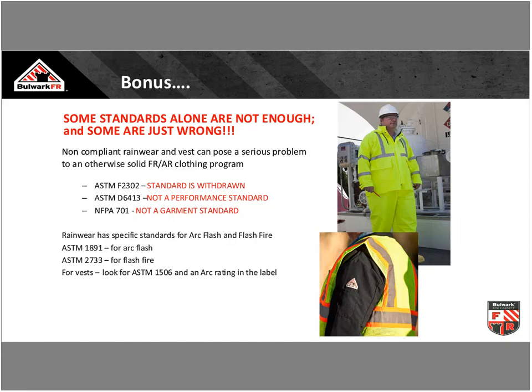The other thing to think about now is we've got a lot of companies that are adopting FR vests, especially ANSI 107 2015 compliant vests. Read the labels. Make sure in that label it tells you that ASTM 1506, that's how it became FR, and you've got an arc rating in that label. If it doesn't have an arc rating, if it tells you some silly things like it self-extinguishes, but there's no arc rating, there's no reference to 1506, wrong vest. We see vests that are compliant to an NFPA 701 standard. That's not even a garment standard. That's a drapery linen standard for the hospitality industry. It's a topical treatment in many cases, and it should not be what your vest is compliant to.